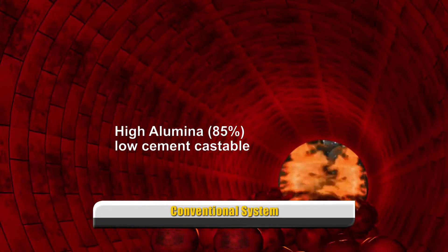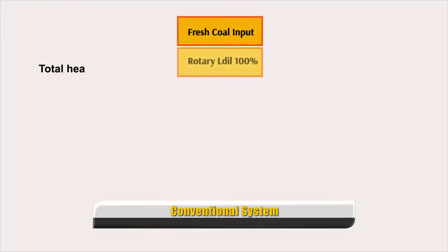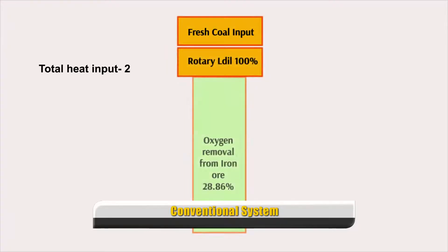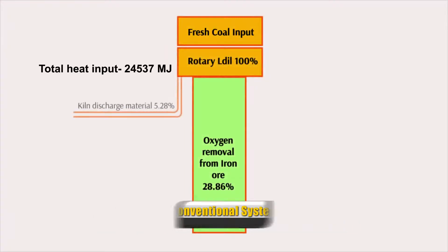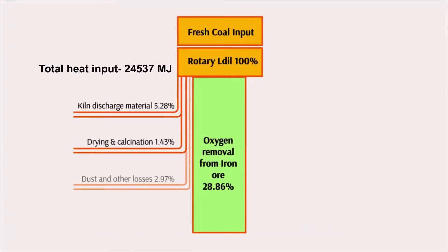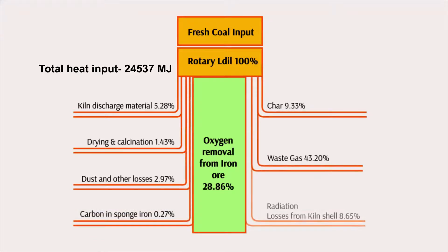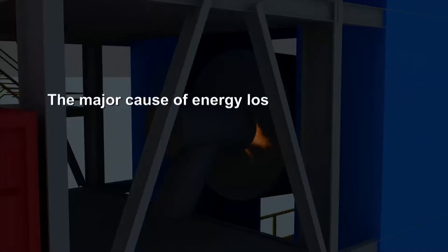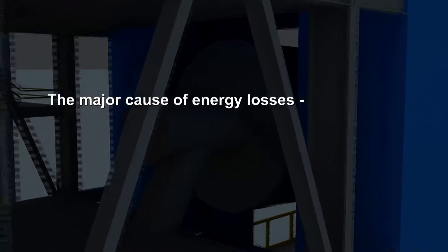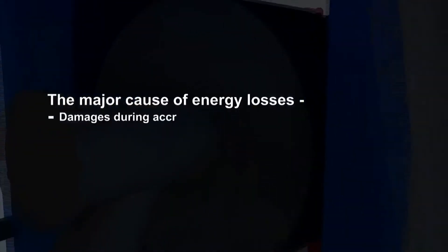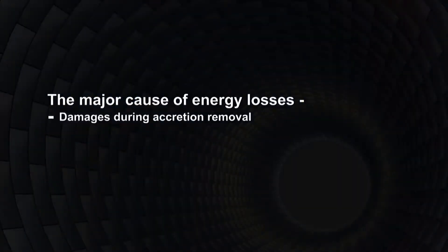The total heat input for a typical DRI plant is 24,537 megajoules, out of which radiation losses from the surface of the rotary kiln are found to be 8 to 10 percent.